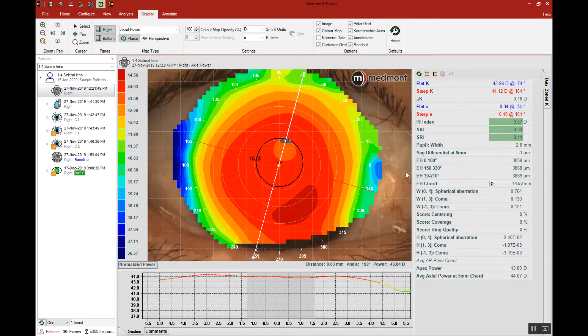How does that work? First, it's ideal if you can select a composite topography. The composite map gives us all of that peripheral corneal information that will help us better predict the anterior chamber depth. The EH chord attribute can be used with a single map, but just be aware that you don't have quite as much peripheral corneal data to calculate that anterior chamber depth.